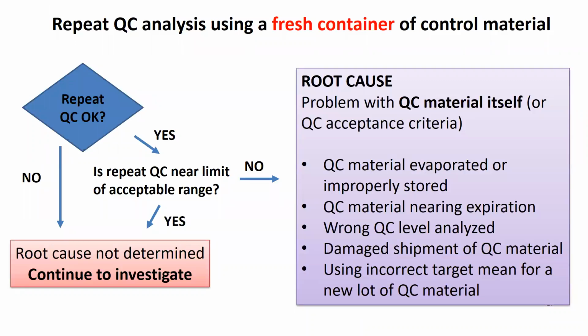One of the first troubleshooting steps you can perform to determine the root cause of a problem is to repeat the QC analysis using a fresh container of QC material. Do not just repeat the QC from the same aliquot or vial of QC material, because this does not really constitute an intervention. Really, the only thing you'll learn by repeating the QC from the same vial is if perhaps the instrument had a misaspiration. So you actually want to go into the refrigerator, obtain a new unopened vial of QC material, and repeat the measurement on a fresh aliquot of the material.